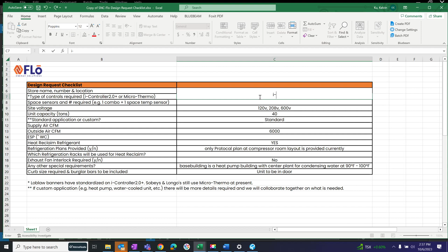So because our unit needs to operate itself without any other inputs, and we do this anyway, we need to watch the space conditions. That will come with the unit, and the contractor will mount it below the unit and wire it up to the unit. The reason that's there is because a lot of times with different stores, when they want Micro-Thermo, they want two sets of sensors and they take an average. When it's iController, they want one set of sensors, and that's fine. So really it was just, we want to know, are you good with one set of combo sensors? That will be in the submittal anyway, but that's really why that was there. Okay, I see.